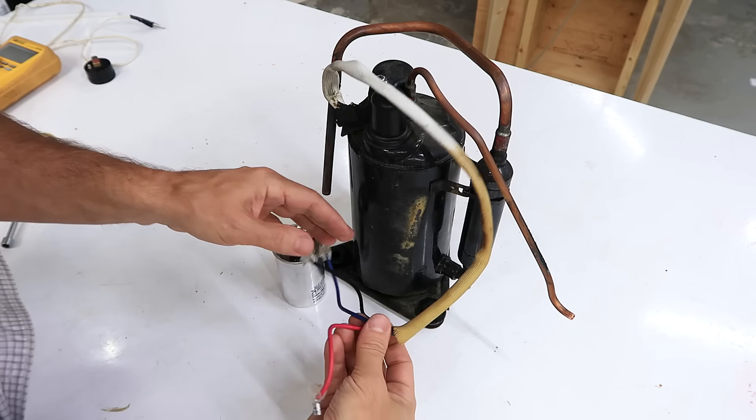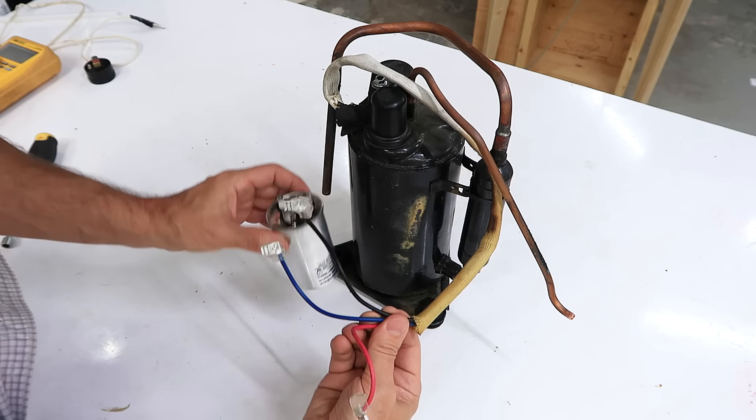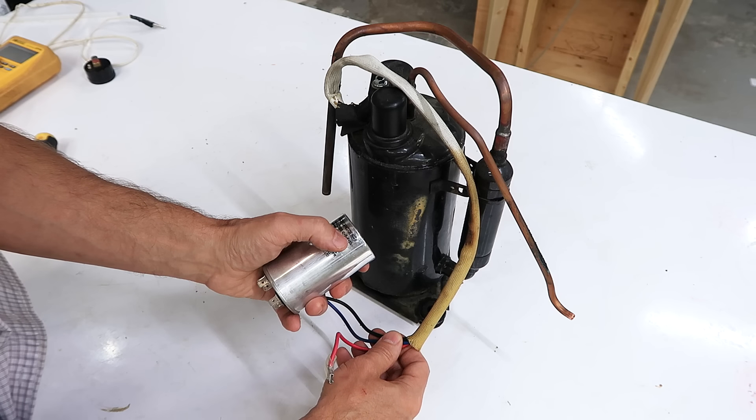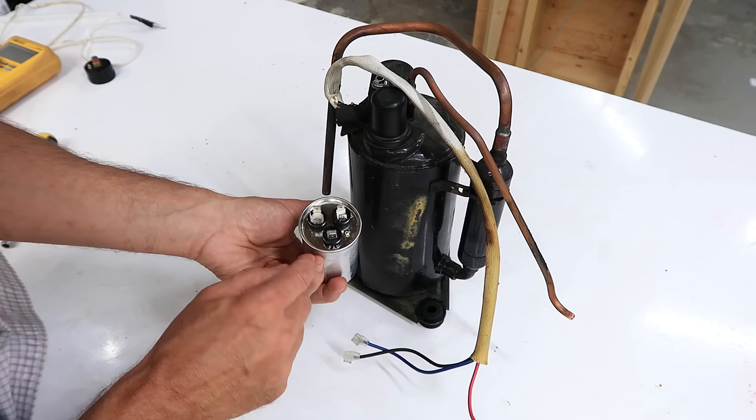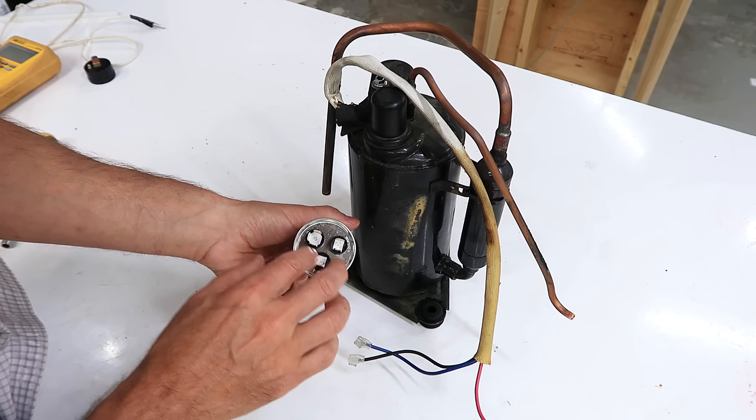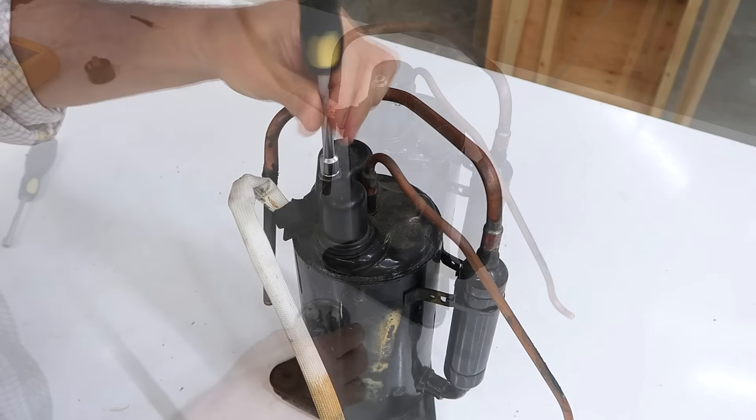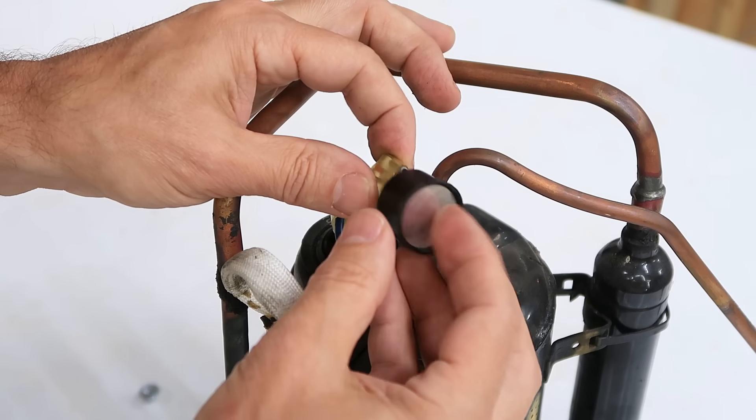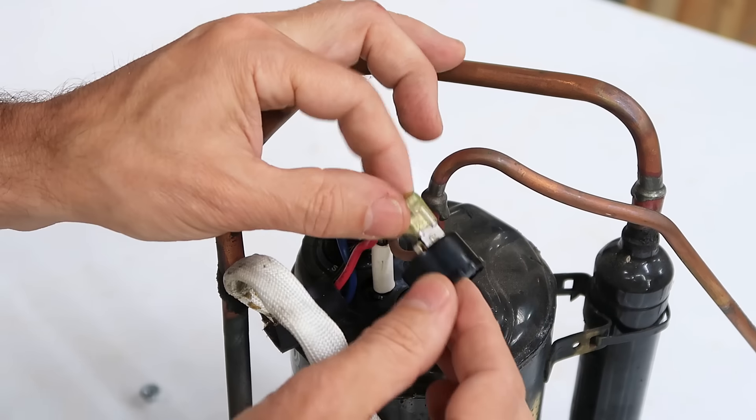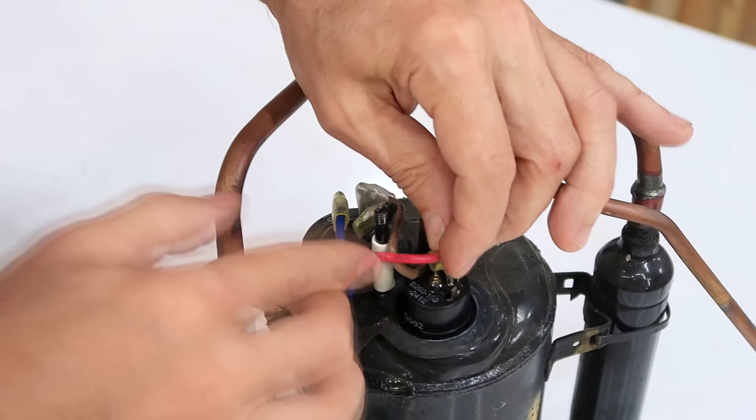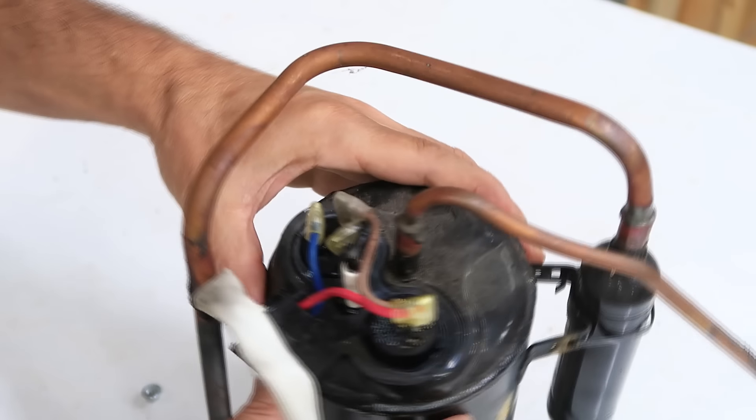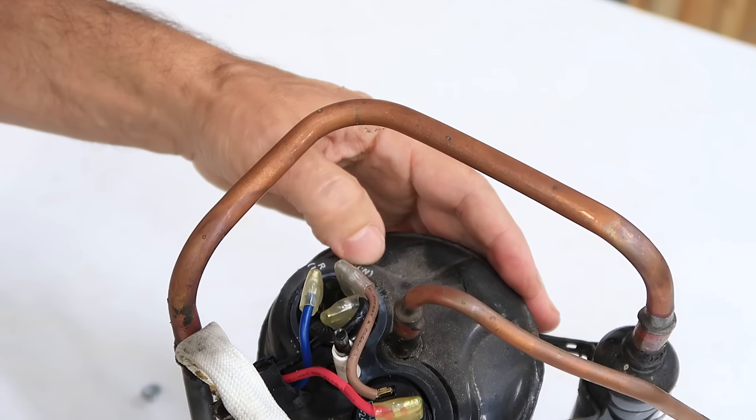The compressor has got three wires coming out of it and there's also this capacitor inside, which is a combined 45 plus 15 microfarad capacitor. One terminal here is labeled fan, so probably the other two are needed for the motor. Under this cover there's this thing here. I'm pretty sure that's an overprotection switch in terms of temperature. We have terminals labeled C, R, and S. Not much of a clue here but C probably means common.